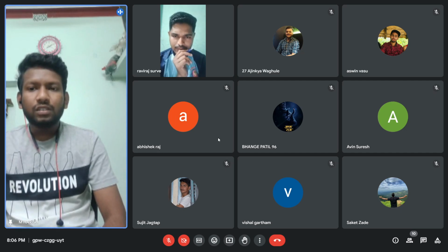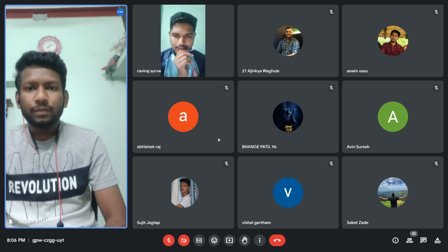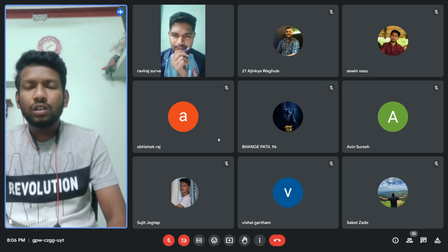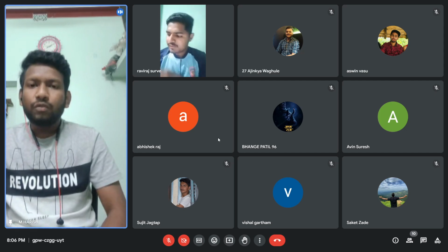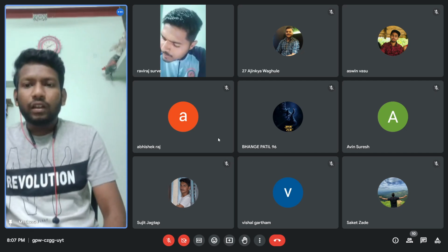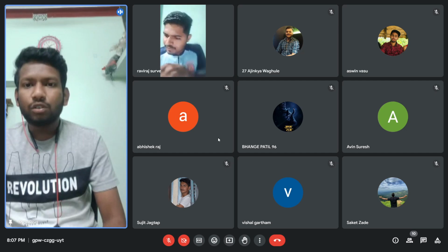Further, it enters a dryer. The dryer is an absorbent. It absorbs the excess amount of moisture present in the refrigerant, and with high pressure, slightly low temperature, the refrigerant enters the thermostatic expansion valve. It is a throttling device or throttling valve which controls the flow of refrigerant, and it is just like an orifice where a sudden pressure drop takes place.